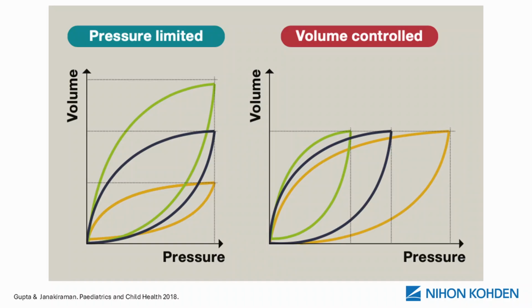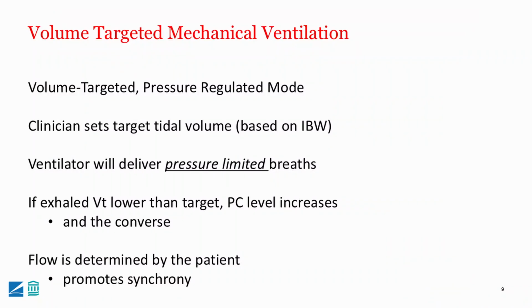So if we take them and put them together into volume targeted ventilation, you kind of get the best of both worlds. You have a volume target that you program into the ventilator so the ventilator recognizes it, but the breaths are actually delivered in a pressure regulated method. The pressure is constant from breath to breath. The flow can actually be variable, improving patient-ventilator synchrony. If the exhaled tidal volume is lower than the target that you set, the ventilator will increase the pressure control to try to get to that target tidal volume. The converse is also true. If the exhaled tidal volume is much higher, the pressure control limit will actually decrease to make sure that we're meeting both those barotrauma and volutrauma concerns.